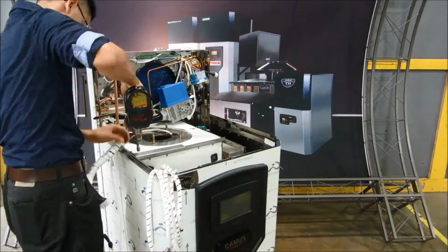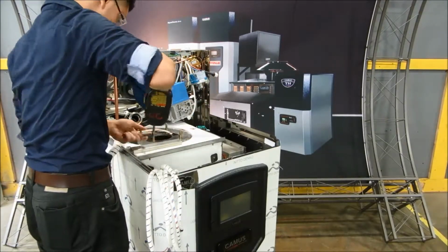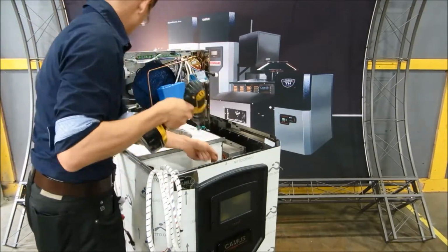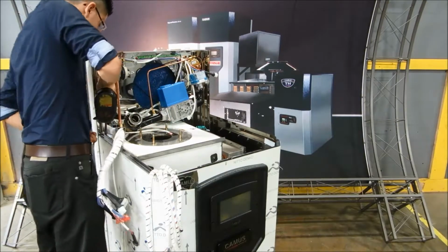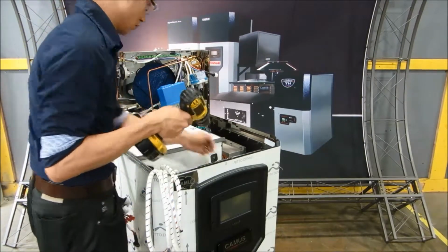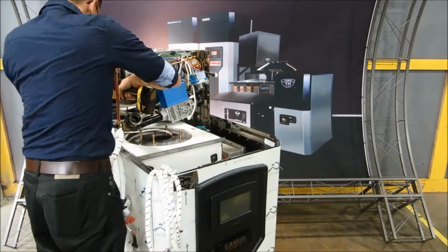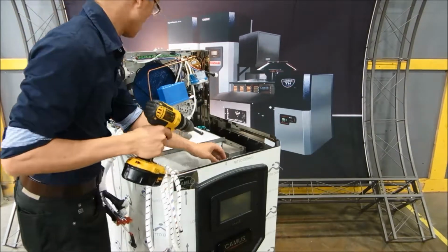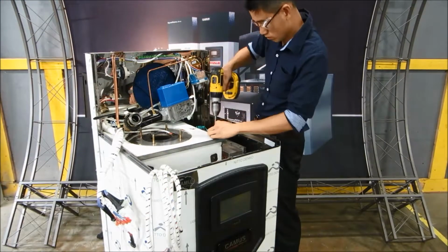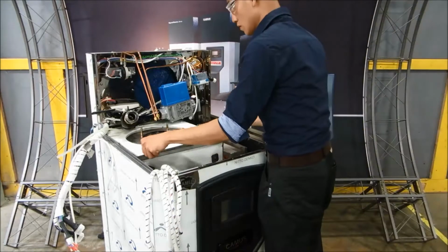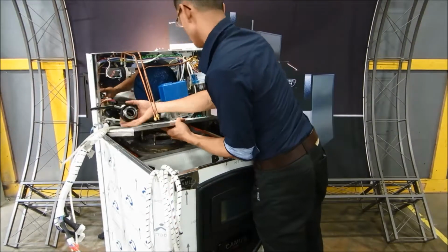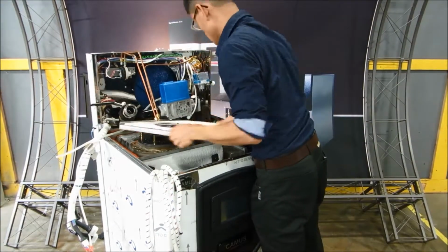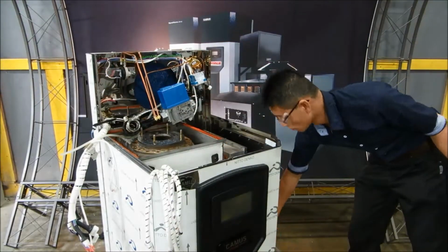To remove the graphite gasket on a Dynaflame, you will need to remove the combustion chamber top panel. Use the 5/16 nut driver to remove the screws around the perimeter of the top panel. Remove the top panel and set it aside. You can now remove the graphite gasket and inspect the interior of the combustion chamber and the heat exchanger.